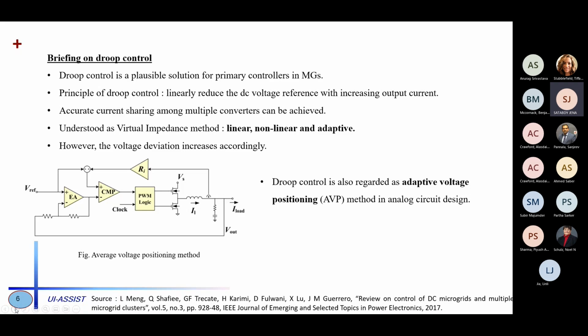When we discuss primary control, droop control is one possible solution for primary controllers in microgrids. It works by reducing the DC voltage reference with increasing load current. With droop, we can achieve accurate current sharing proportionate to the power rating of the converters.